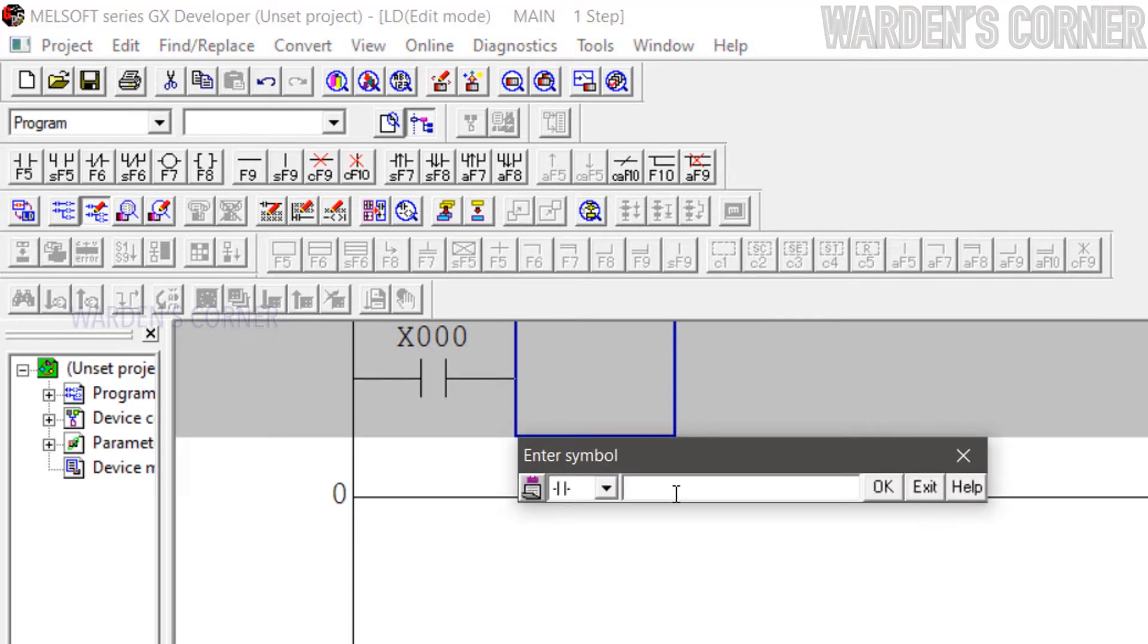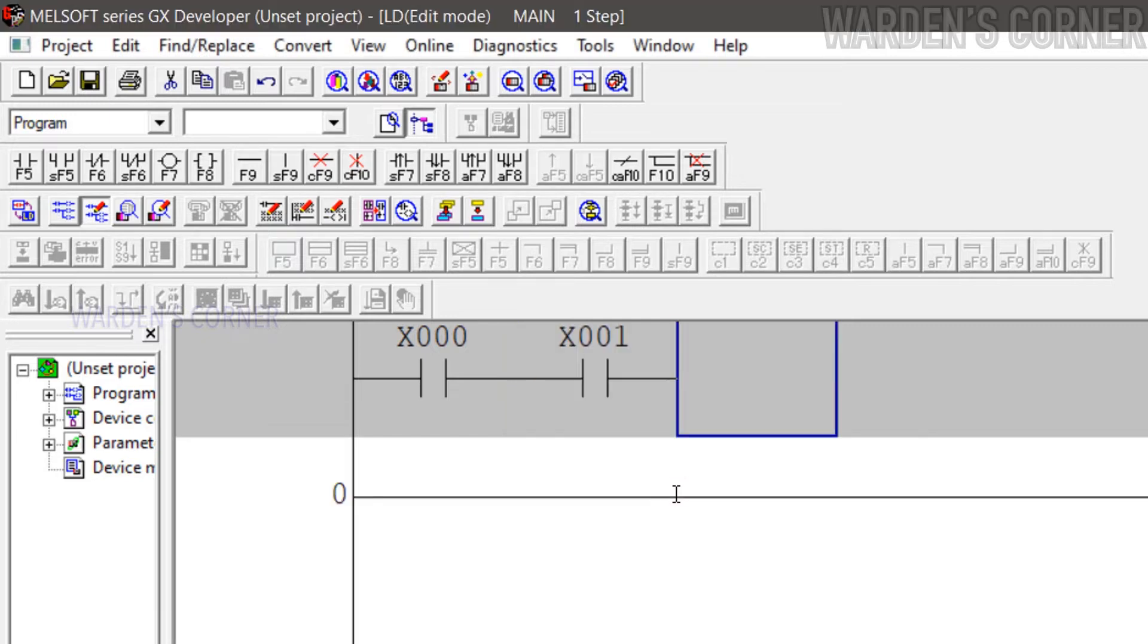Next, add another Normally Open Input Contact, type X1, this will be the stop push button. Note that we use a Normally Open Logic Contact for stop push button because in actual connection of input devices, stop push button is a normally closed contact.